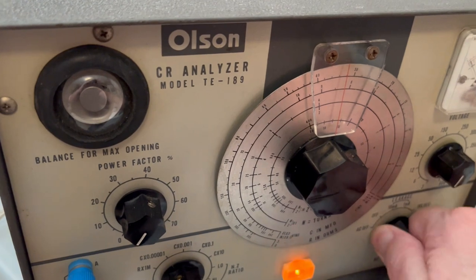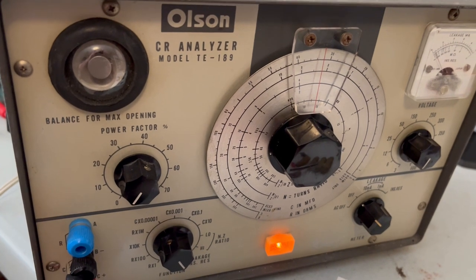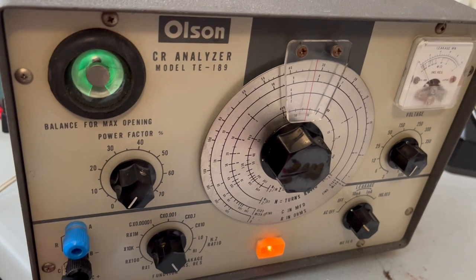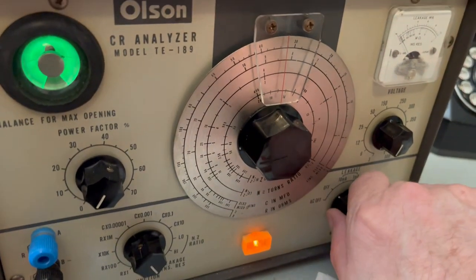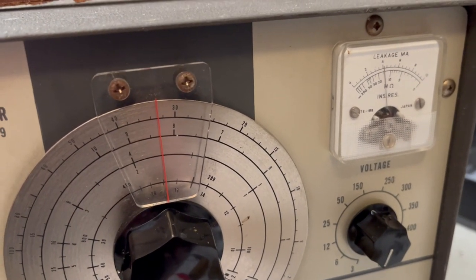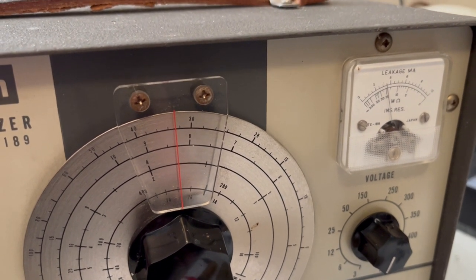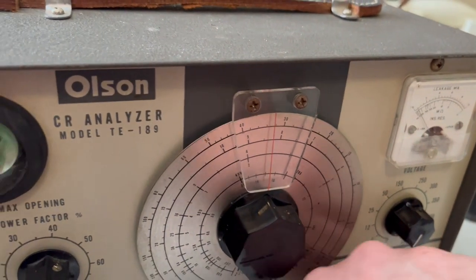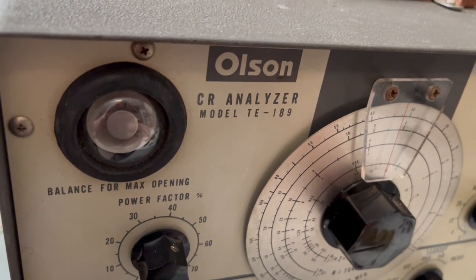I shut the power off on it. Okay, see how long it takes for that eye to open this time. It opened pretty quick. It's opened already, so let's go ahead and throw it. Oops, not this one, this switch. Well, it's not popping right back down either, so yeah, this one appears to have some leakage issues as well. I'll disconnect this one, move on to the next one.